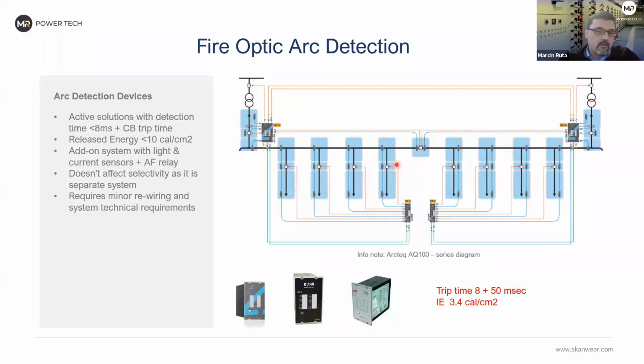So if you go to the hardware solution for this specific problem, we can have a fiber optic arc detection. And because it's fast and it's a separate system, we don't have any problem with selectivity with it. And we can keep the system relatively safe because it's still something, but it's 3.4 calories in this situation, so let's say below 4 calories. So it works very nicely.